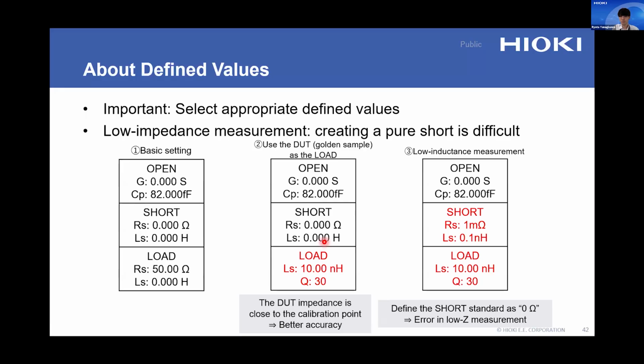Also, for low impedance measurement, the defined value for short calibration is very important. A short standard is never a perfect 0 ohm. It always has some residual impedance. If this is defined as 0 ohm, that residual impedance becomes a measurement error. In such a case, it can be effective to enter the residual impedance of the short device as the defined value for short calibration. You can see here the residual value can be input into the defined value.